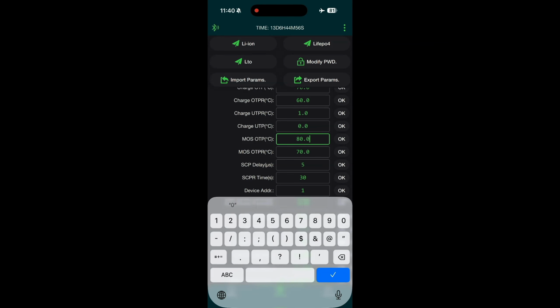So if you wanted to change it to say 60 as a reset value, then you can go back and change this to 70 if you want, okay? But the over temperature protect must be higher than the reset value when you're trying to change the values.